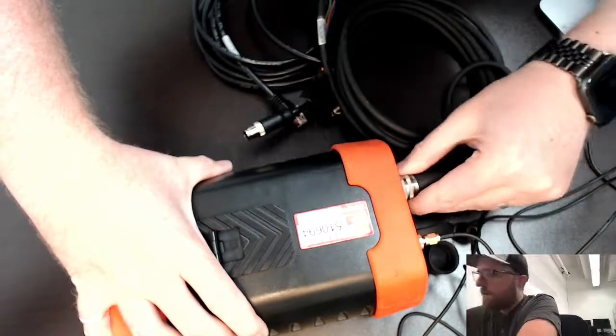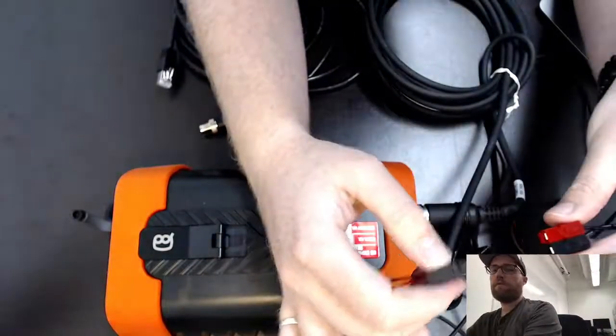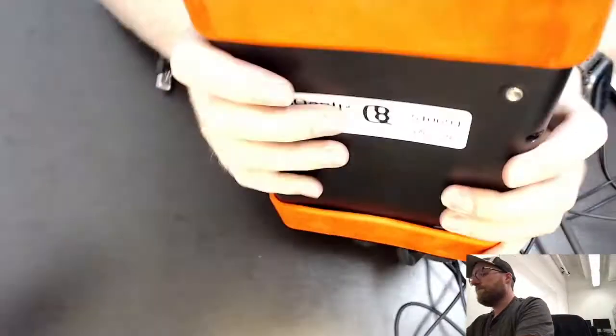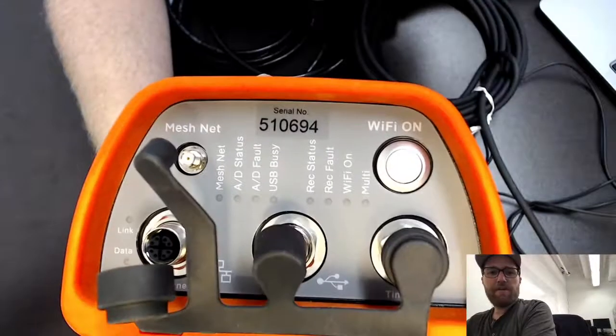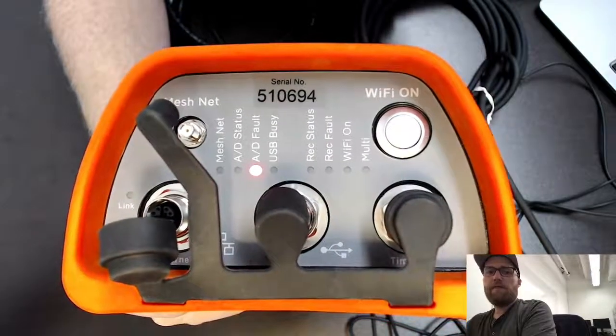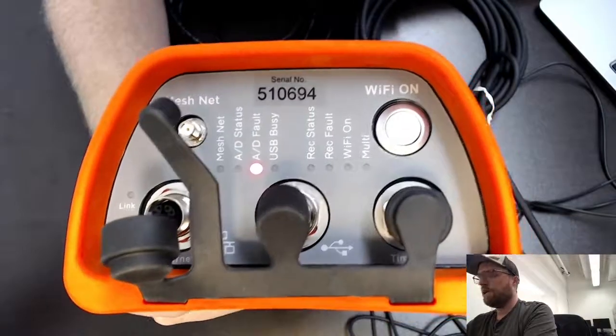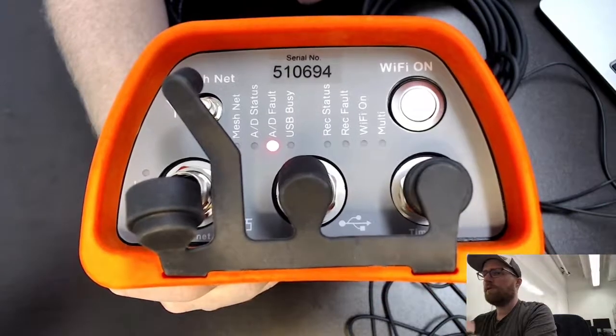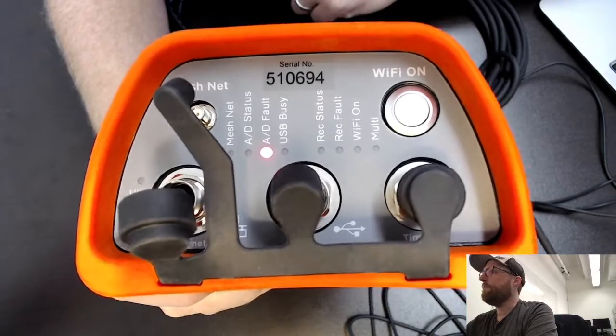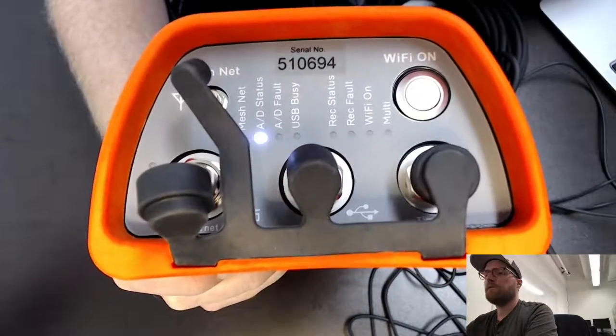Alright, this can be a bit tricky to connect. They have to go in exactly the right position. There you go. And this turn, wait for it to click. So let's connect. So I've got a 24 volt power source set up already that way. Connect this too. So once it's plugged in, then we should see some activity. Not yet. I think it takes a few minutes. There we go. It can take a few minutes on initial setup. There's actually a capacitor in here that has to charge up. And that's used as a kind of temporary battery, to help with power fluctuations and to allow it to cleanly shut down if the power is lost.